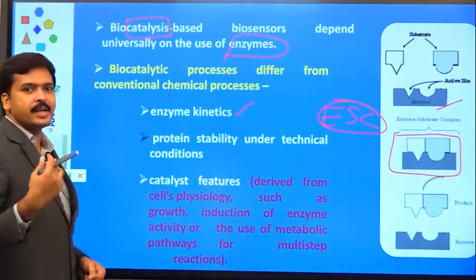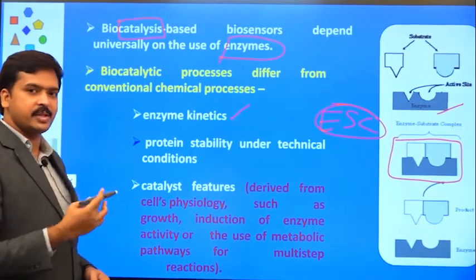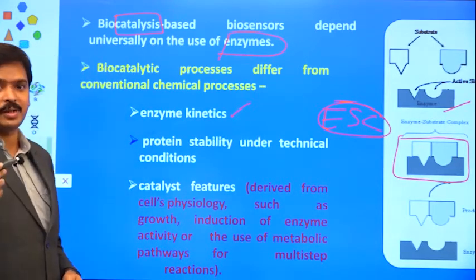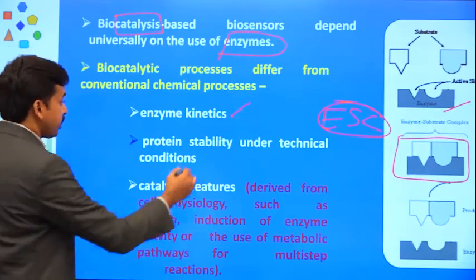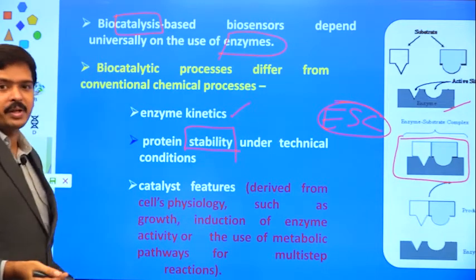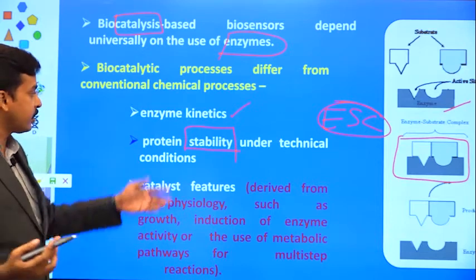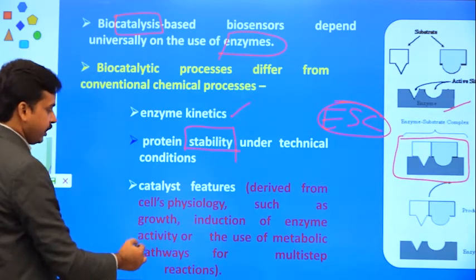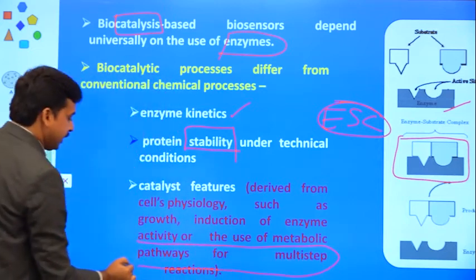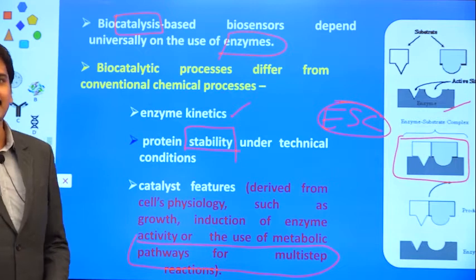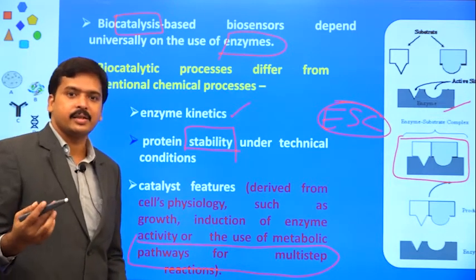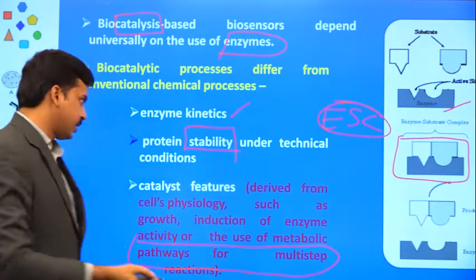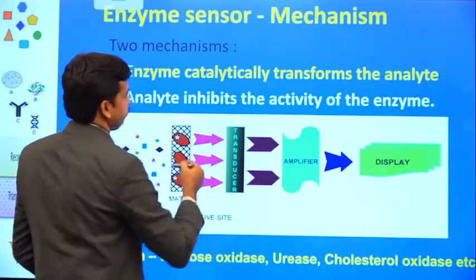Enzyme kinetics — inside the body, the rate of reaction in the presence of enzyme is at one level, but whether the same level is maintained outside needs to be considered. Concentration fluctuations must be accounted for when designing. You also need to consider how stable the enzyme is at room temperature — if the biosensor temperature increases, does the enzyme lose its activity? Additionally, enzyme activity may use single steps or multiple steps, since a single step may not always give a prominent result. Recently, biocatalysis-based biosensors are being prepared with multiple enzymes.